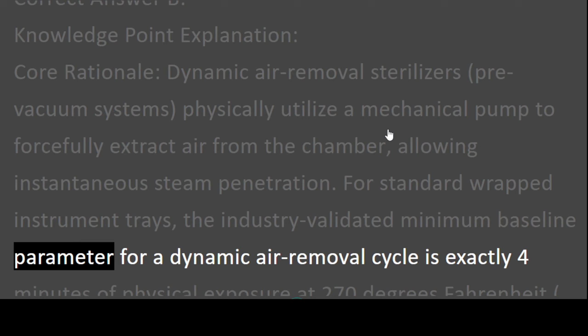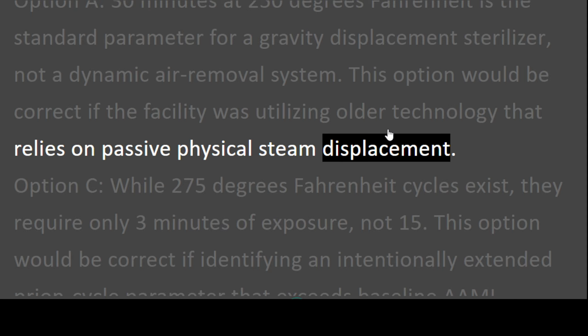Trap analysis. Option A. 30 minutes at 250 degrees Fahrenheit is the standard parameter for a gravity displacement sterilizer, not a dynamic air removal system. This option would be correct if the facility was utilizing older technology that relies on passive physical steam displacement. Option C. While 275 degrees Fahrenheit cycles exist, they require only 3 minutes of exposure, not 15.